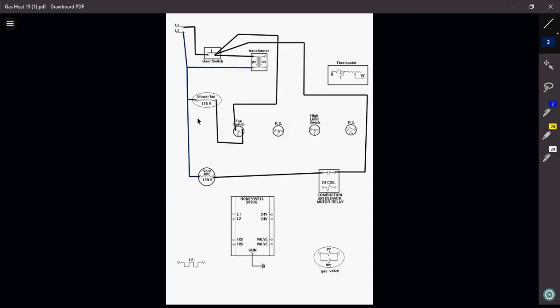Okay, so what we just did is we just took care of the three main loads in our furnace. We took care of the primary side of the transformer, we took care of our blower fan, and we took care of the vent motor, also known as the inducer motor. Okay, so what do I need to do with the rest of this?